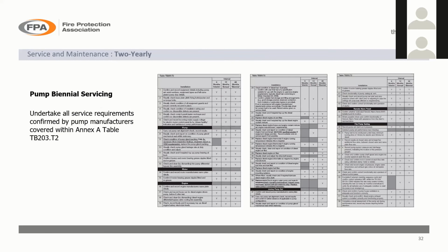I'm moving on here. I'm conscious that I'm going over the time limit, so if you're sticking with us, thanks very much for doing that. There is a 2 yearly requirement in TB 203, which is to undertake a service of the pumps. TB 203 table T2 gives quite a detailed list of requirements for pump servicing. It doesn't actually cover everything. What you need to do is get a sprinkler pump specialist in to carry out some of the servicing. You can organise that with your maintenance contractors.